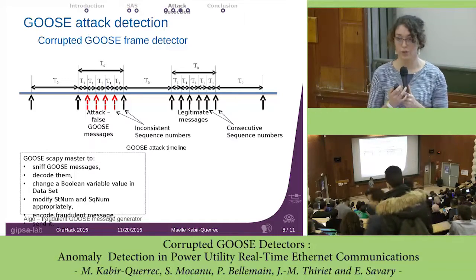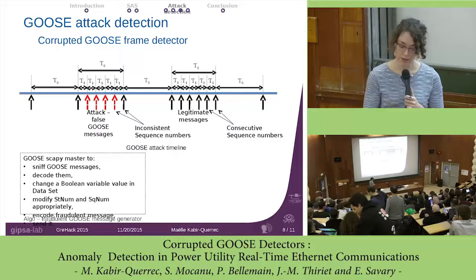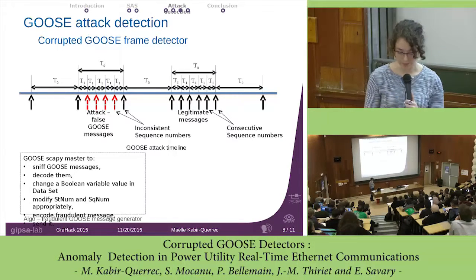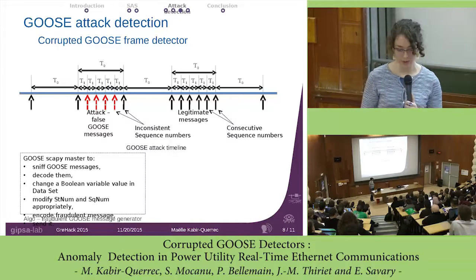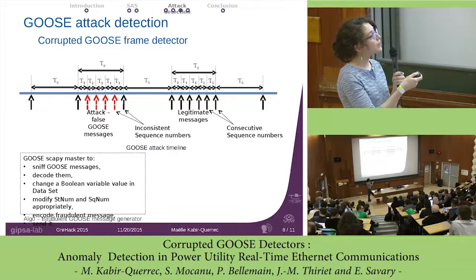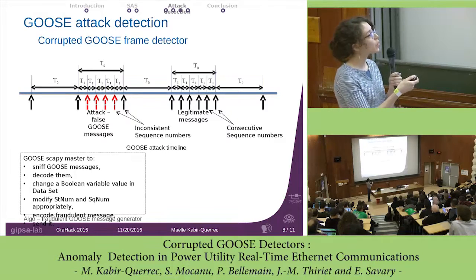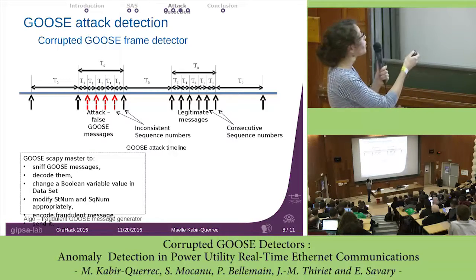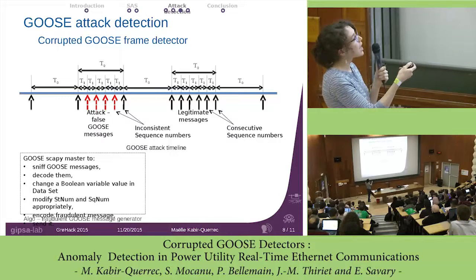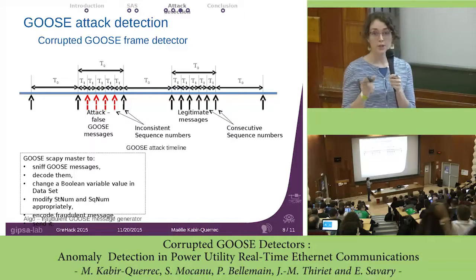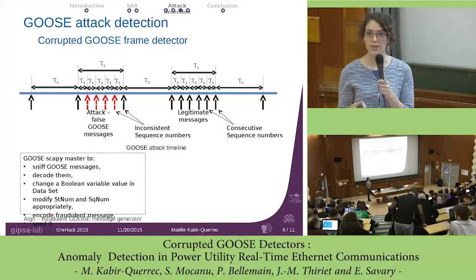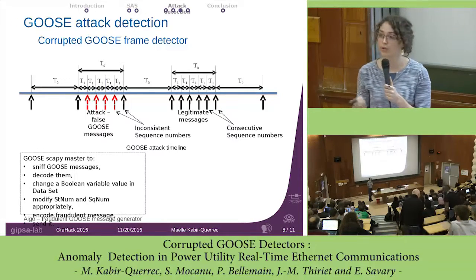This is about the detector of corrupted GOOSE messages. In a normal transmission timeline, when the system is in stable condition messages are repeated with the same content. An attacker can use a time slot between two legitimate messages to send a false GOOSE message with false content — for example, to take control of a circuit breaker or another device in the process. Even if the attacker is very precise and takes care of changing the counters in the PDU — incrementing the state number, resetting the sequence number to zero, then incrementing it — when the next legitimate message arrives, it will be detected because there will be inconsistent sequence numbers.